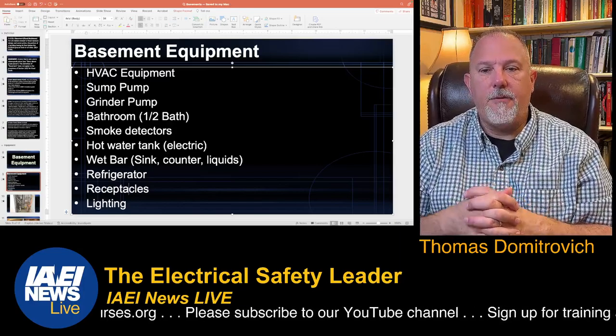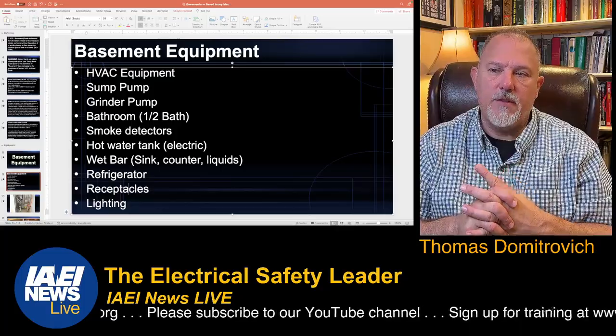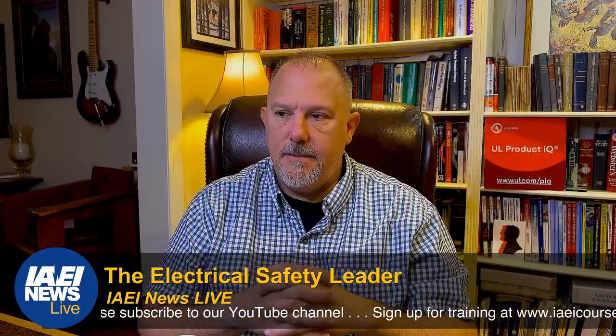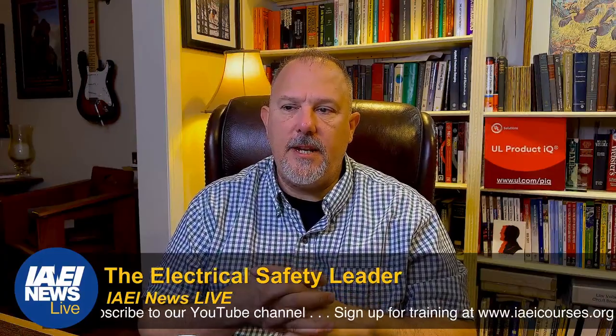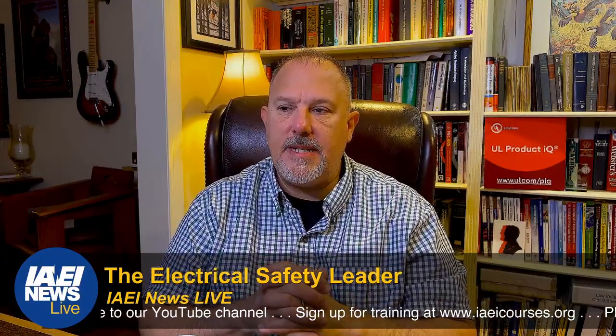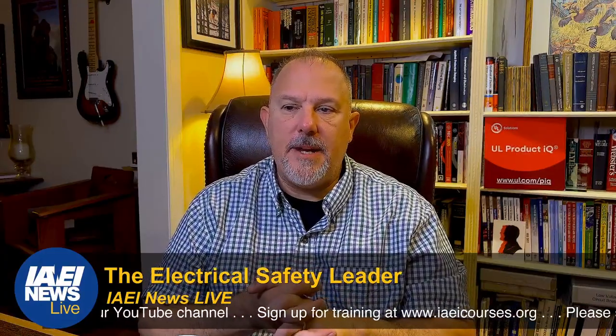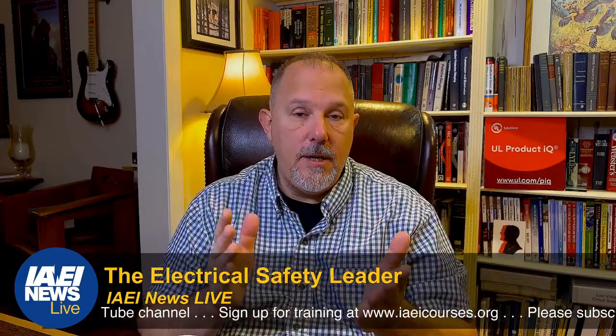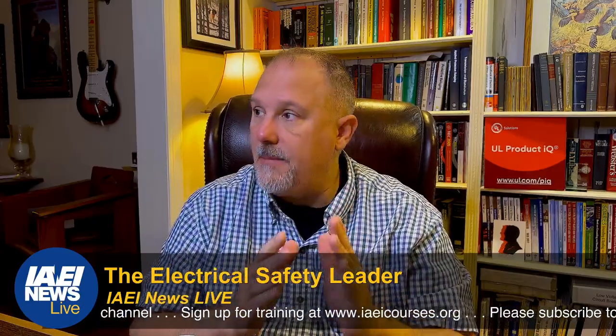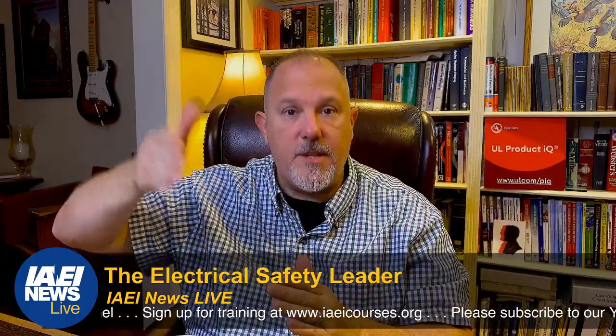Air conditioning and refrigeration - why wouldn't 422.12, central heating equipment, be there instead? It says central heating equipment, other than fixed electric space heating equipment, shall be supplied by an individual branch circuit. So this relates to the circuit requirements for a basement.